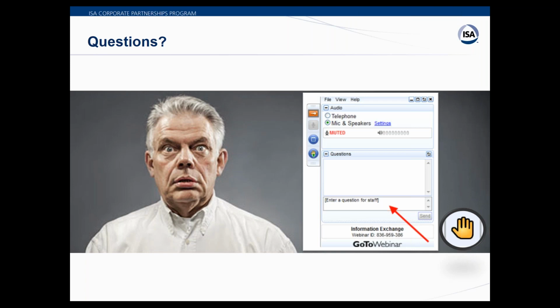It's possible to calibrate too often. I'm not sure, am I allowed to say that? But in some cases, you don't need to calibrate as often as you think. If it's an SIS system, you may not have that flexibility. You may have to calibrate it more often as proof. But if you calibrate something and it's out every single time you go out there, then you need to shrink that interval. Instead of calibrating it every year, check it again in 6 months.